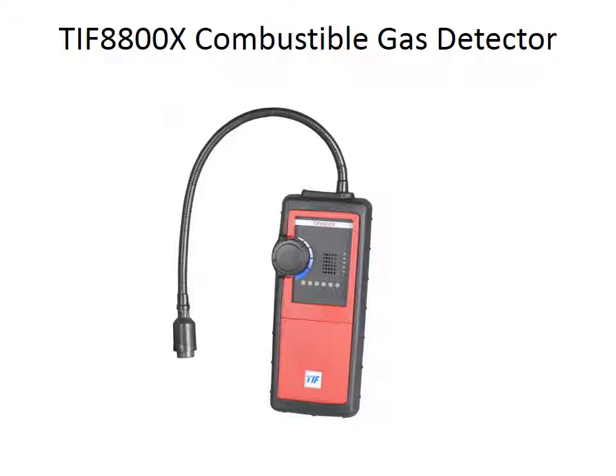It takes a 20-30 second warm-up time, and then you start to hear a tick rate. That tick rate is what's going to indicate whether or not there's natural gas. As you get into a natural gas environment, that tick rate increases. After the warm-up period, you want to turn that knob clockwise to where your tick rate goes to just a normal pace, and it usually ends up being the second to last selection going clockwise.